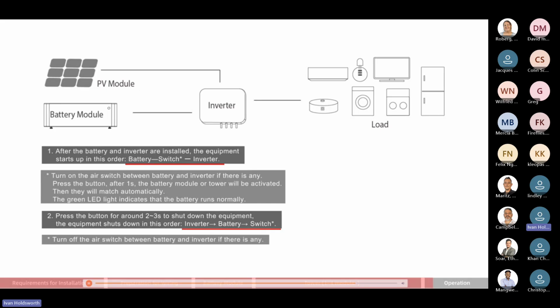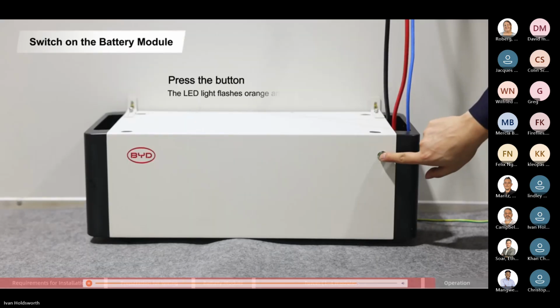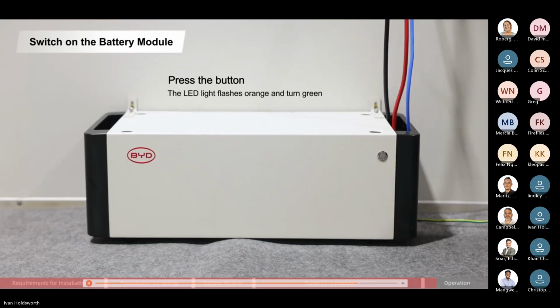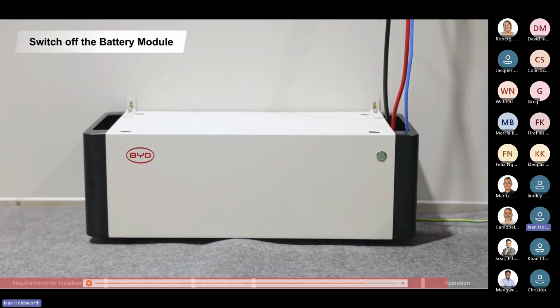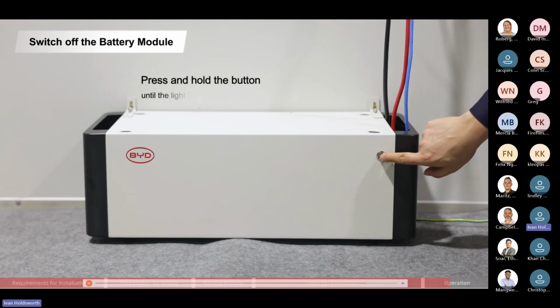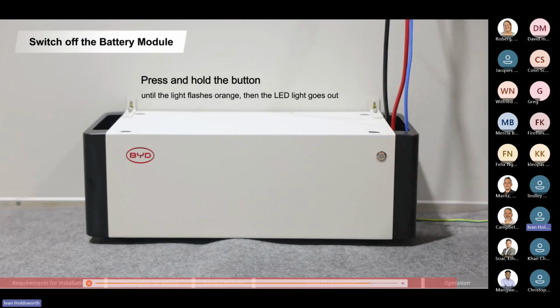And here are just the turn-on procedures. Green means the battery's happy. If you've got multiple batteries in a bank and they're all green, that means the batteries can see the master and the master can see the inverter. If they're flashing orange, it means they're waiting to connect to the inverter and the bank is also waiting for the master to connect.